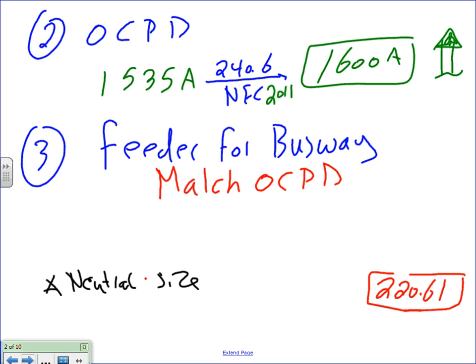Now, Chris, because I'm higher than 800 amp, when I size my feeders, I have to match the overcurrent protection device. Up to 800 amp, I could have sized the feeder based on 1535. But obviously, this is higher than 800 amp. Because we're higher than 800 amp, our feeder must match the overcurrent protection device that protects the busway. So, any question, guys, about the overcurrent protection device before we move into the feeder? For the feeder, I say match the overcurrent protection device. So you take the 1600, but they don't make a 1600 amp THHN conductor. They don't have them in the market.